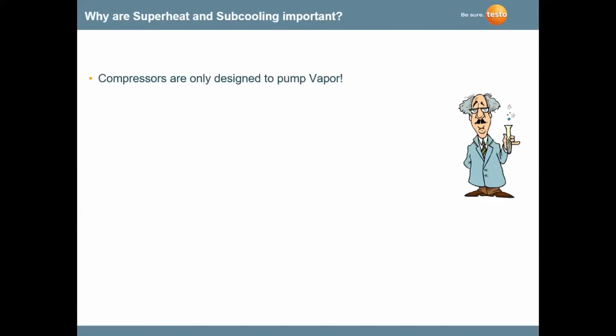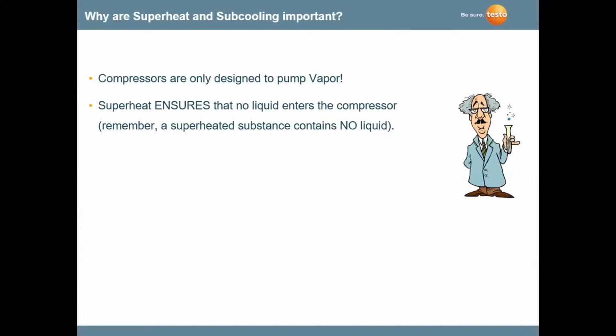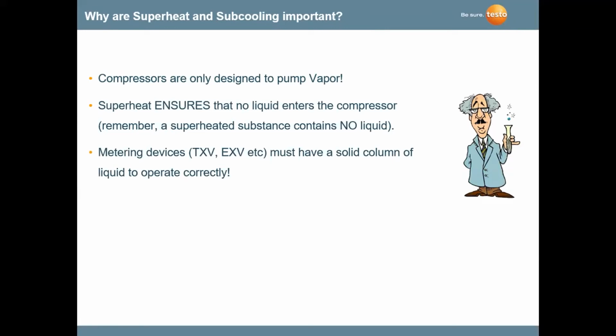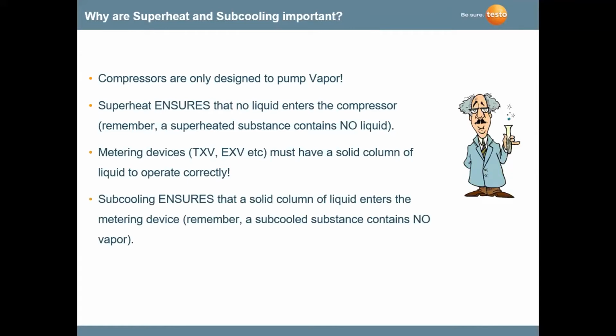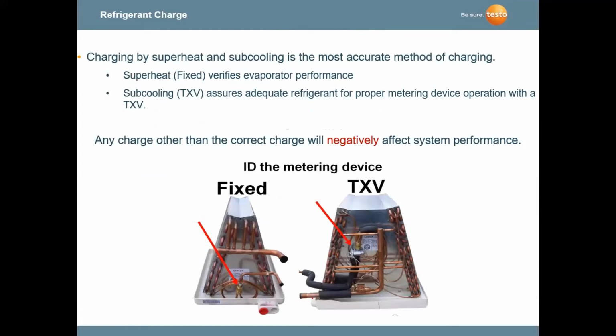So why are we measuring superheat and subcooling? Well, compressors are only designed, as we all know, to pump vapor. Superheat ensures that no liquid enters the compressor, and the metering device must have a column of liquid to operate properly. And subcooling ensures that a solid column of liquid enters the metering device. In a lot of cases, you may be dealing with fixed capillary or piston type metering devices. Most systems today are TXV, but superheat verifies evaporator performance. Subcooling ensures adequate refrigerant is going to the metering device.